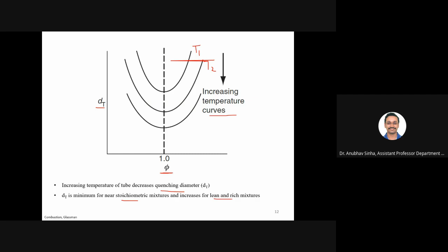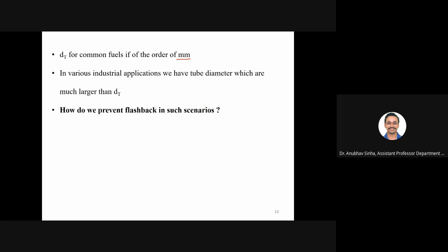Fine. So this d_T, the quenching diameter, if you look at the flame speed and do all the calculation, is roughly of the order of a millimeter or 2 millimeters. Whereas if you look at industrial applications, like a boiler or gas turbine, we have tube diameters of the order of centimeters or meters. In simple terms, it is much higher than d_T. So what do we do? How do we stop flashback? Suppose your d_T required is, let us say, 5 mm, I'm just taking a simple example, and your tube diameter is 5 centimeter.